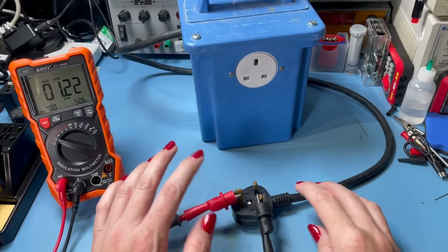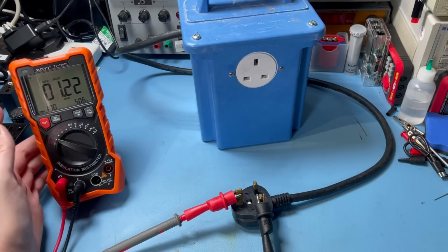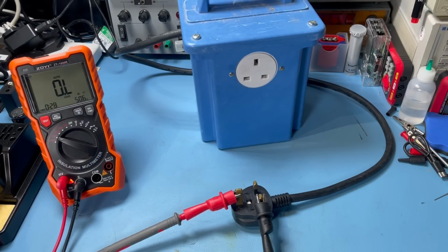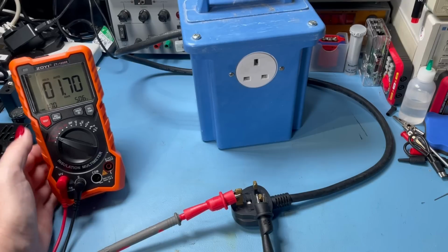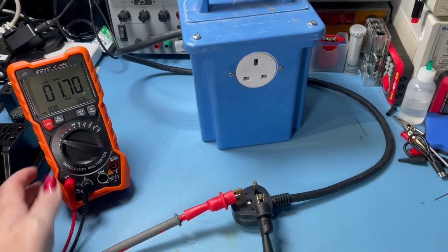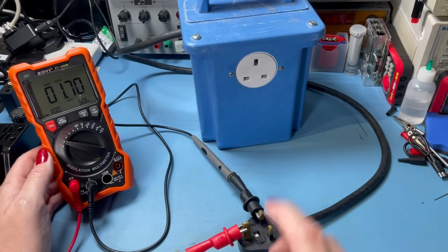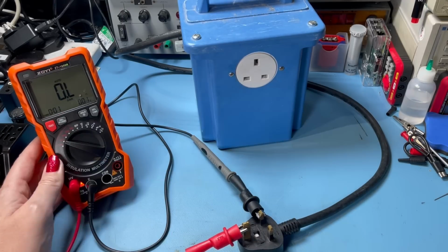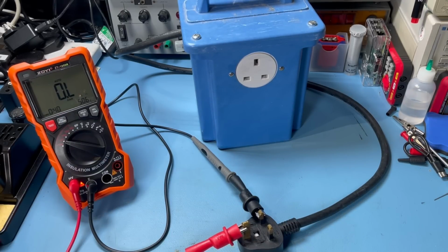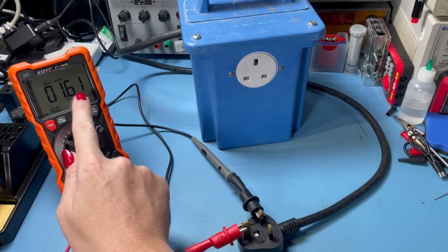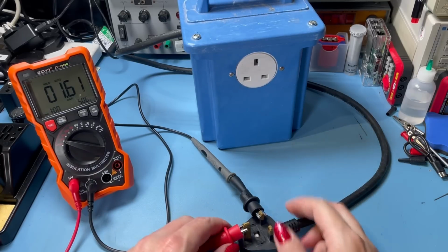500 volts DAR live to earth. Let's go. Right, fantastic, and we've got a DAR of 1.70. I would expect it to be really good on this. You've got to be very mindful though while you're testing not to touch the plug or the device under test. So we're going to do the same test again, neutral to earth, DAR, go. Again, very good, 1.61 DAR. Excellent, just what I would expect.